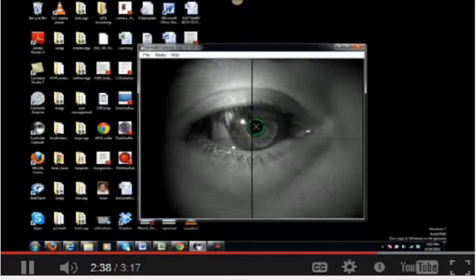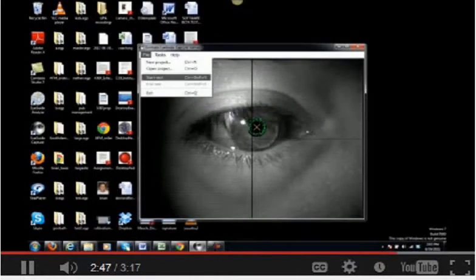If you choose to recalibrate, check the camera and LED positioning again, make sure that the headset is secure, and check that there is no interference between the DVR and camera. Remind the participant not to move his or her head. When you are comfortable with the new positioning, go back to File and Start Test. The participant will go through the same calibration process as before.